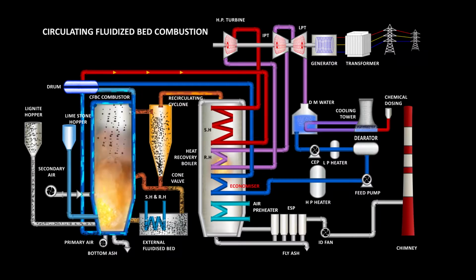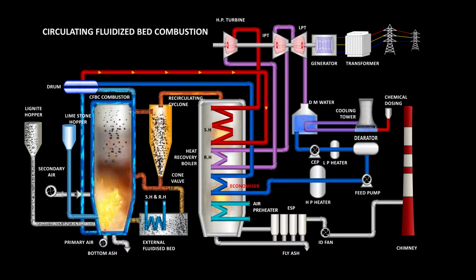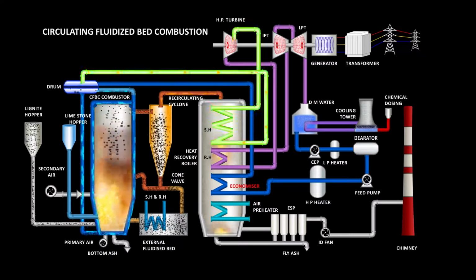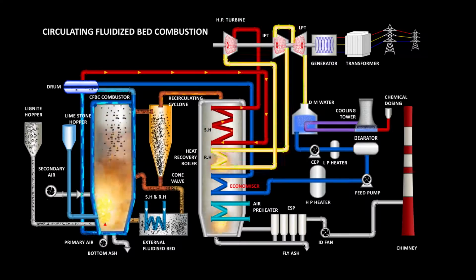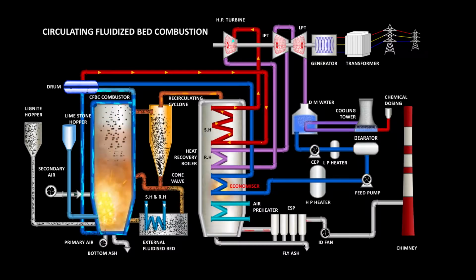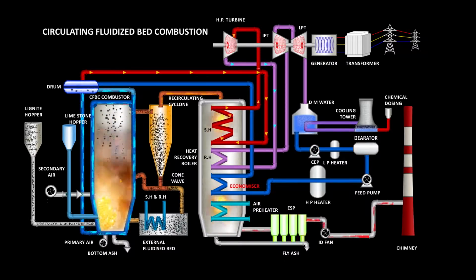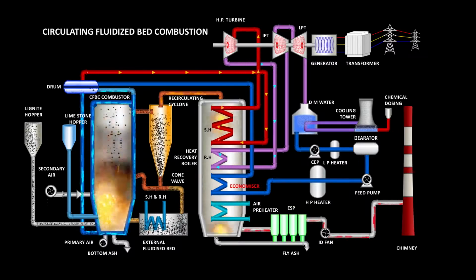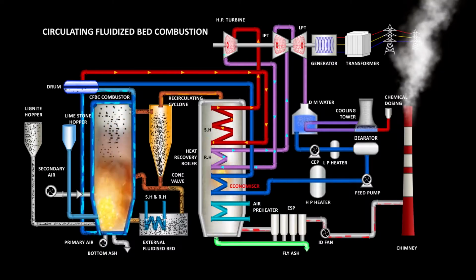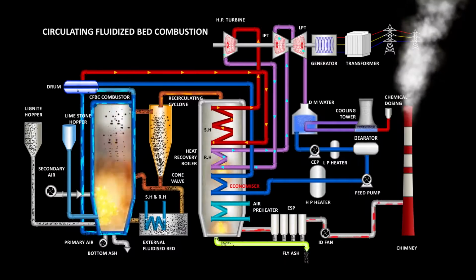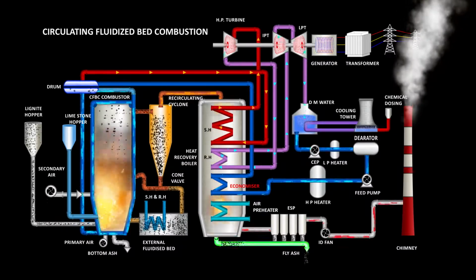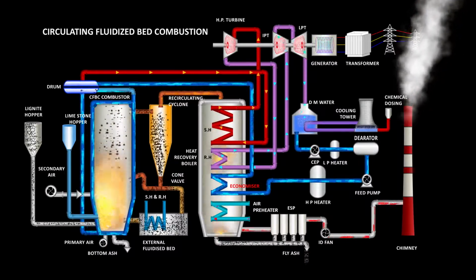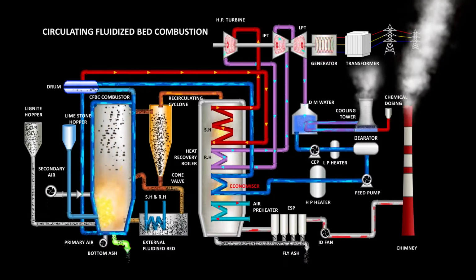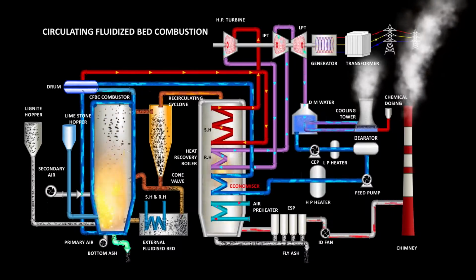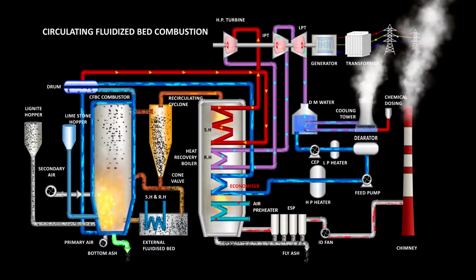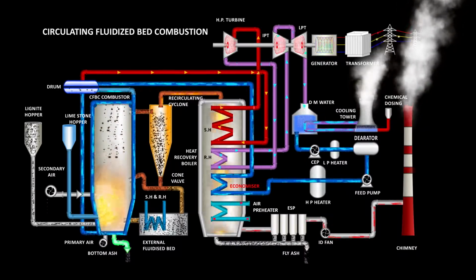The hot flue gas goes out of the combustor, passes through the second pass, where it transfers heat to the superheater, reheater and economizer. Then it passes through the air preheater, electrostatic precipitator and goes into the atmosphere through the chimney. The fly ash collected in the electrostatic precipitator is disposed of by a dry ash collection system. The bottom ash is collected and cooled in ash coolers, which are placed at the bottom of the combustor, and then it is transported to the bottom ash silo by conveyor belt for disposal.